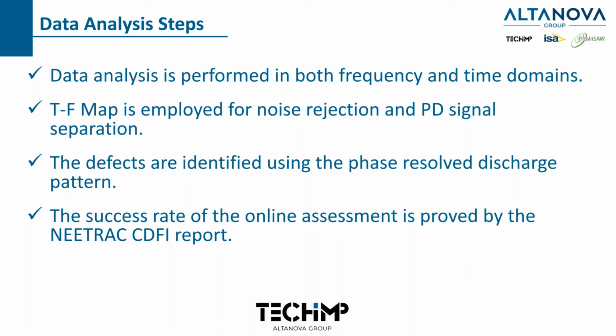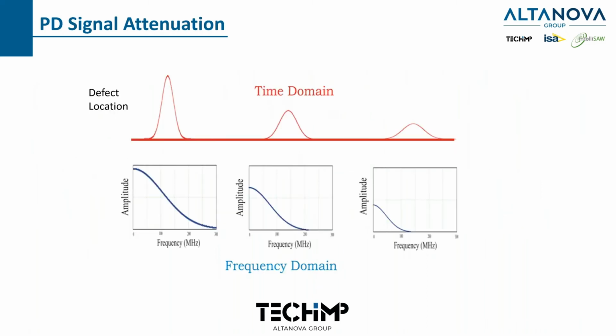Then we identify the defects using the phase resolved discharge pattern. I'm going to show you what that is. It's basically the signature of the type of PD. The first thing to remember is that with all RF signals, as we move away from the source of partial discharge, amplitude and frequency are going to decrease, just like any RF signal. So as we move away from the PD source, amplitude and frequency will decrease.